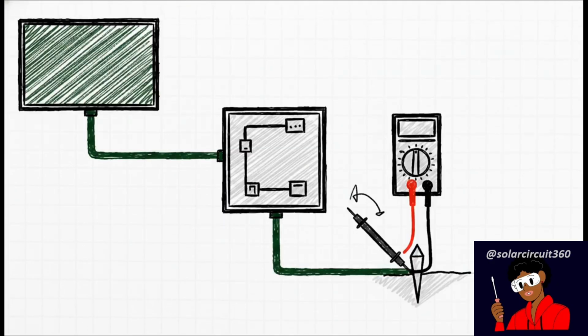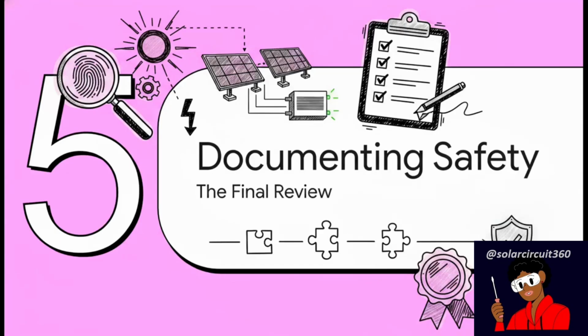And now, step 5, ground continuity. We absolutely must physically verify the connection between the ground rod, the ground bus bar, the inverter chassis, the equipment enclosures, and the array frame. Honestly, grounding is probably the most misunderstood area of solar installation. Just connecting a grounding wire to a terminal does not guarantee safety. We have to physically measure the continuity to confirm that fault currents have a highly reliable path straight back to the ground. Without that path, your protective breakers might not even trip during a fault, which leaves the entire metal chassis dangerously energized.